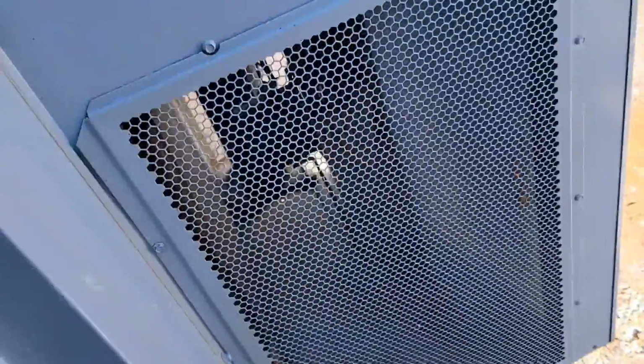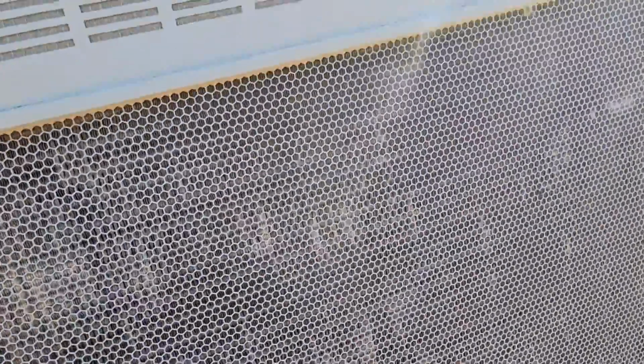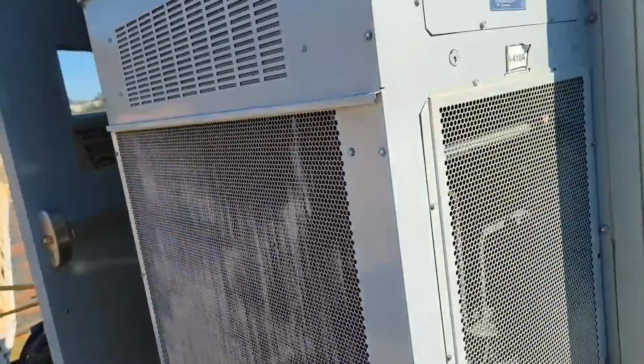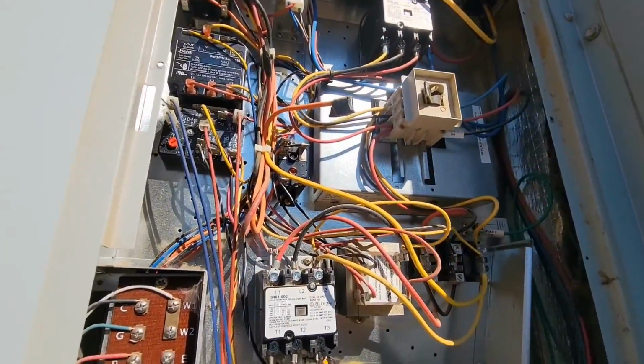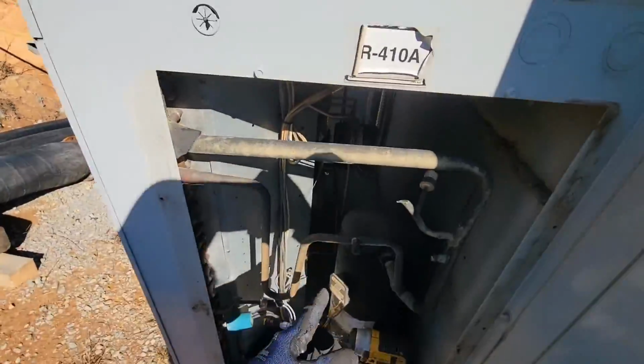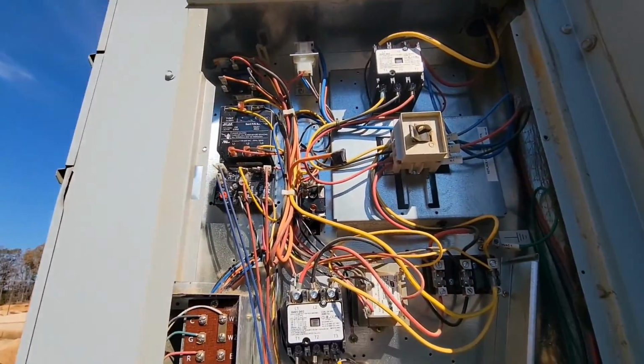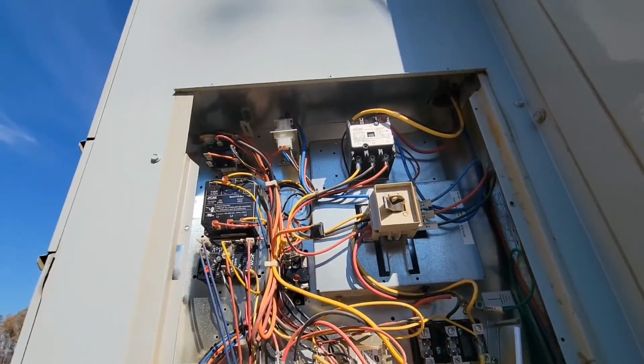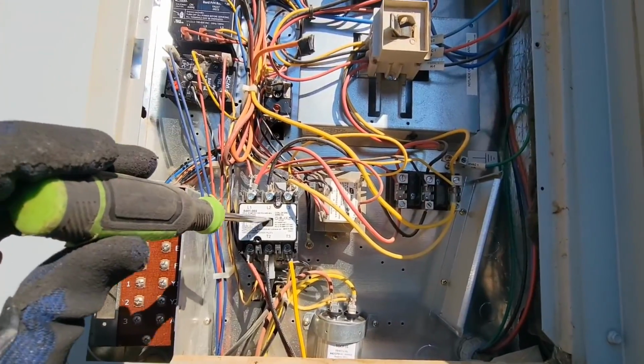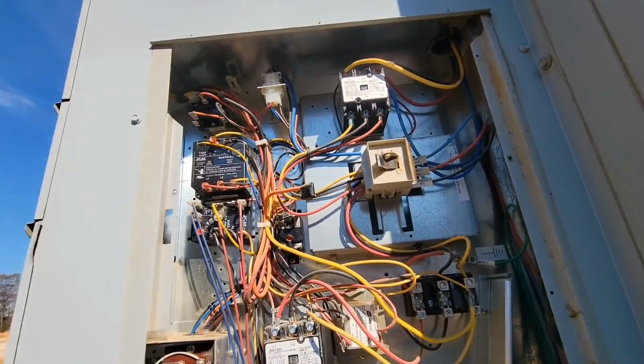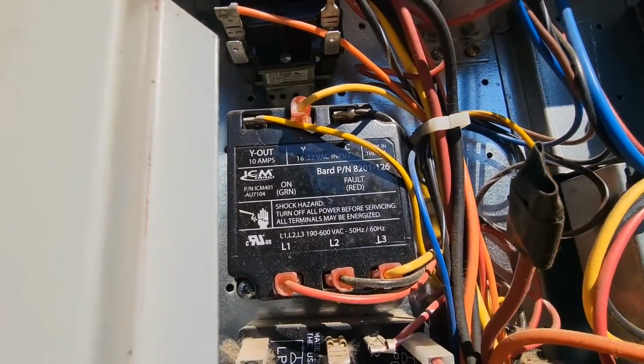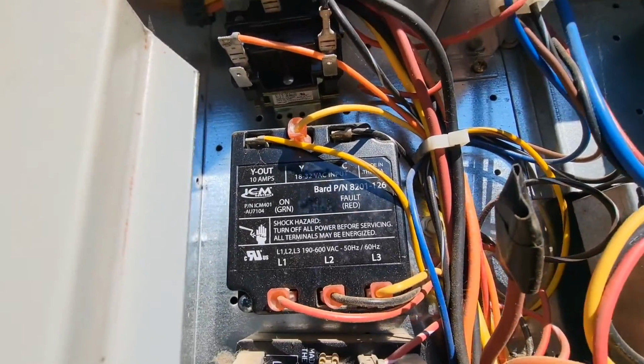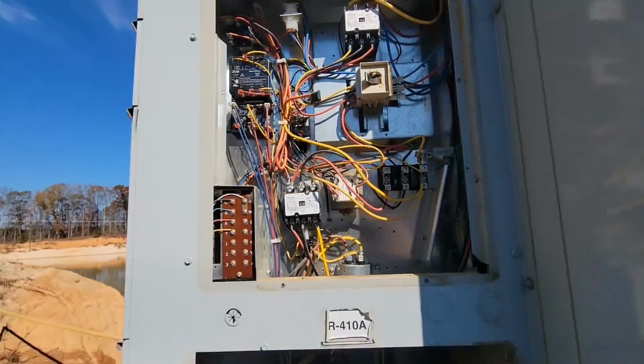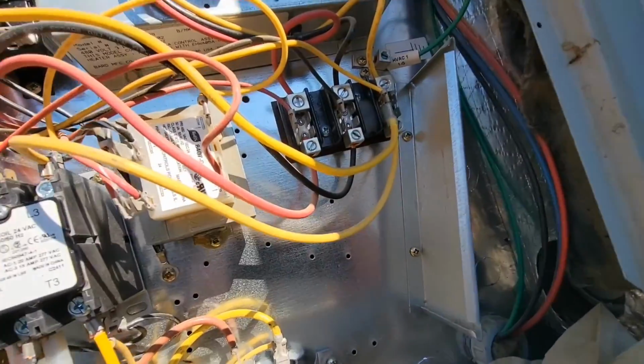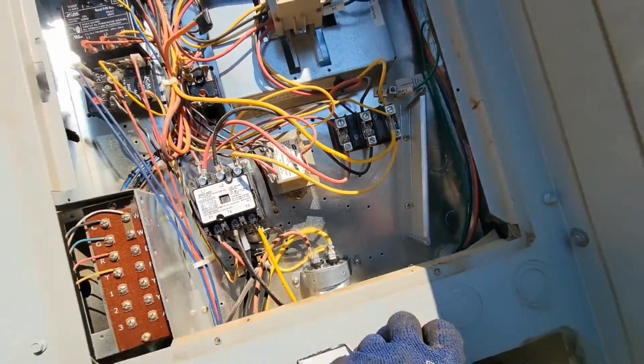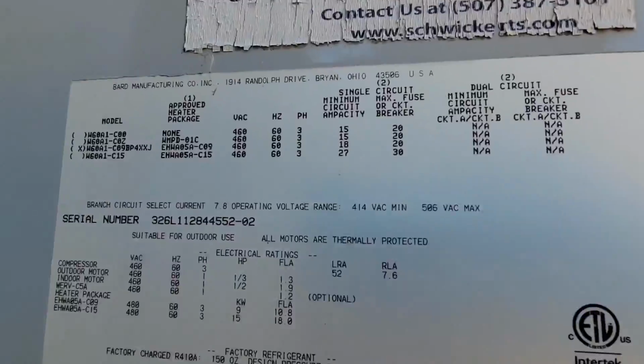All right. Set up a ladder, take some panels off. Okay, so got it all opened up. We want to make sure there's some refrigerant, so we put our gauges on. We want to make sure there's power, so check with the meter, or you know what I like to do? Just push the contactor in. No power, no light on the little phase monitor there, so we need to check the breaker. It's 3-phase. We got 3 legs of power coming in, so let's find the breaker.